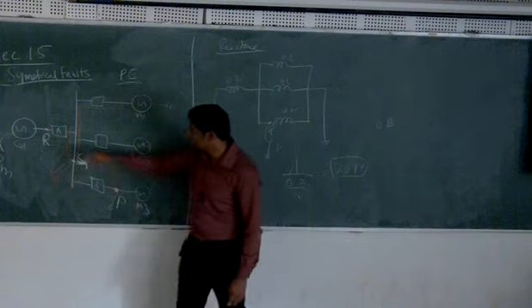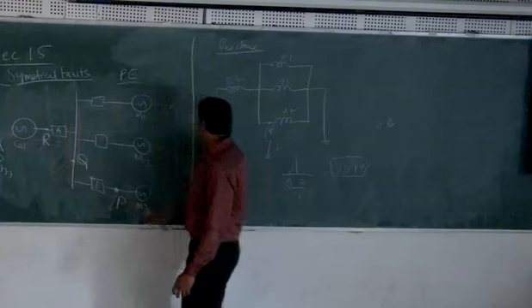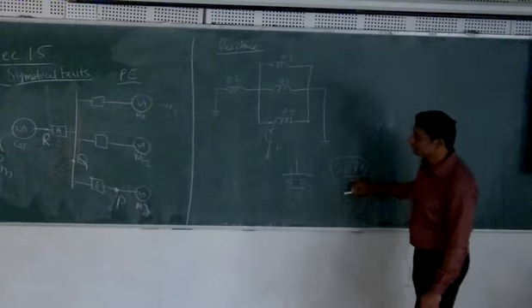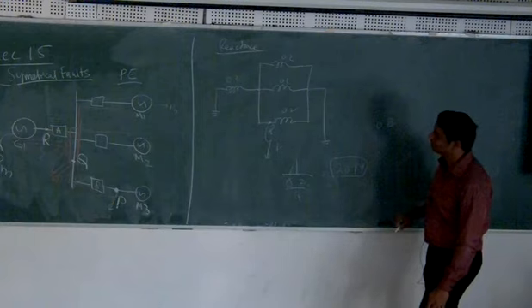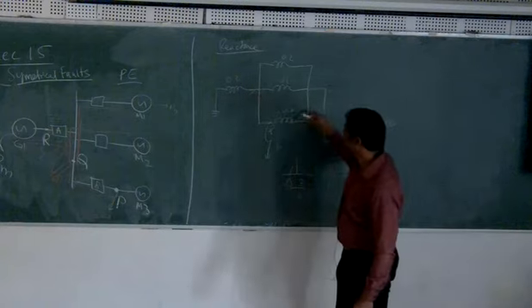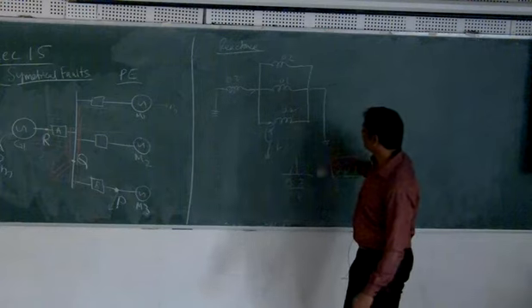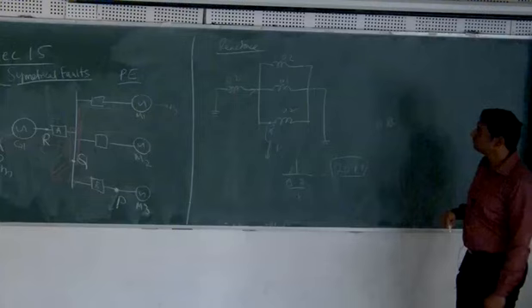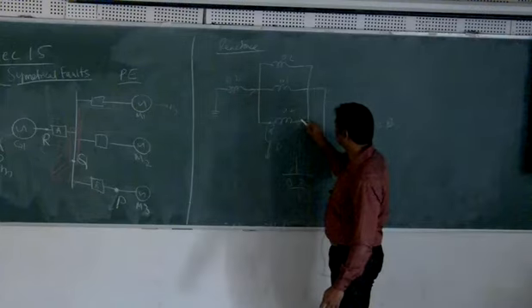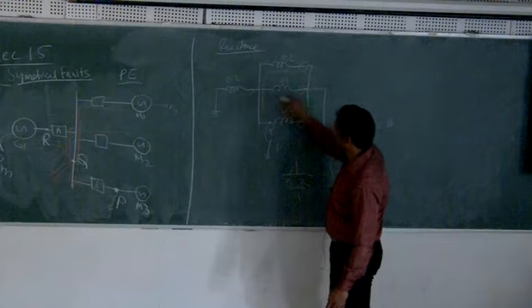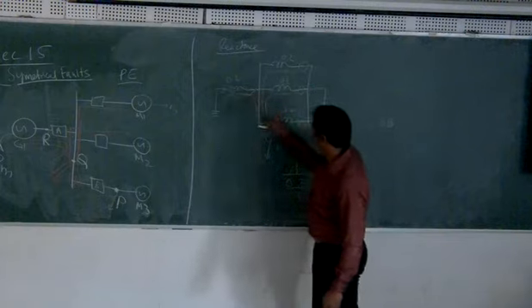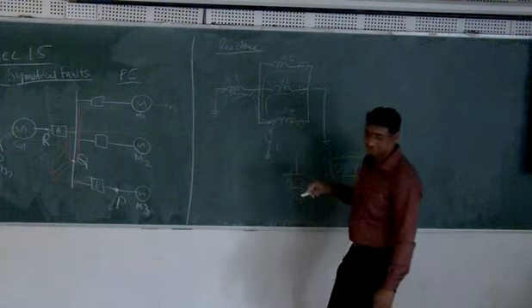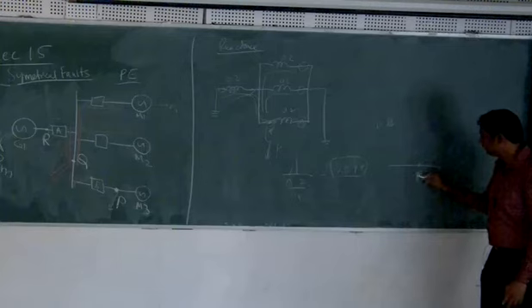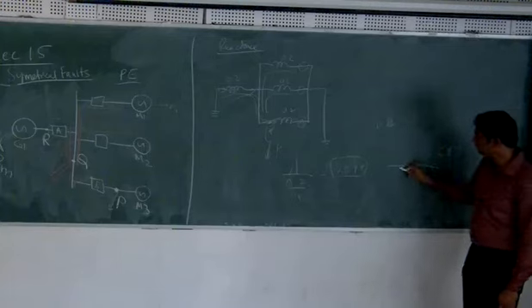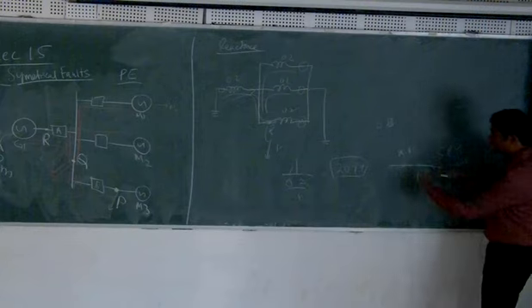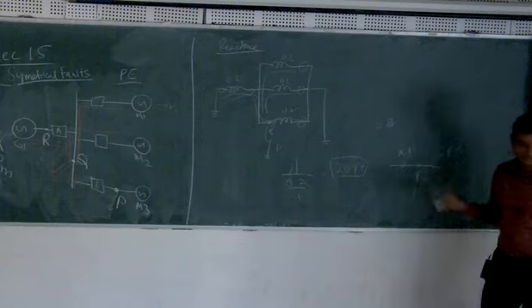So how much per unit in circuit breaker A? That will be in this 20 per unit. You have to solve this to find this current. Actually, in our calculation there is a machine here, a machine here, a machine here. This current is like this, and then there is another machine here. So three are like this and one is like this. If you look at the point B, 5 per unit is coming from the left, and then 15 per unit is coming from like this. And then the total fault is 20 per unit. So this kind of thing.